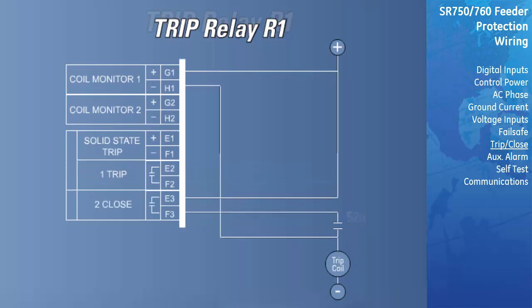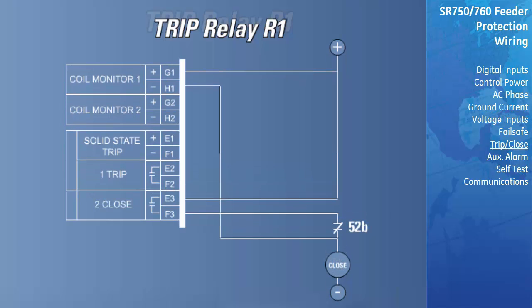The close contact, R2, is designed to energize the close coil of the breaker whenever the relay issues a close command. The close command can be initiated by the auto-reclosure scheme in the relay, any remote close signal, or the voltage and frequency restoration functions of the relay.